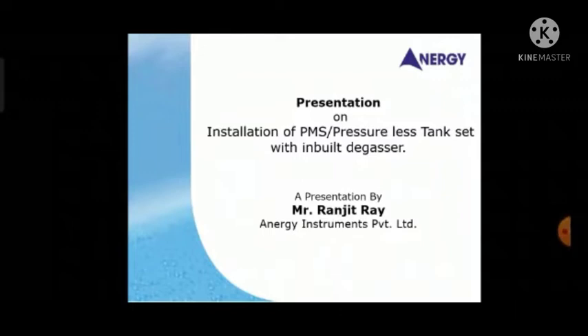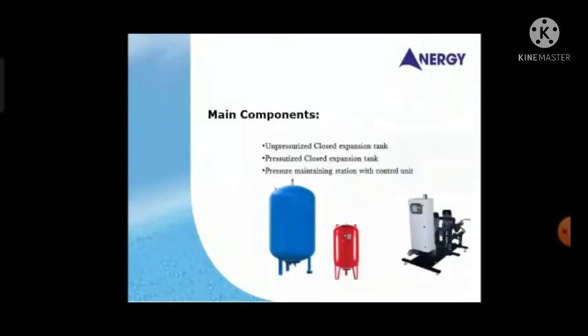This video is for installation guidance for the pressure maintaining station, which is also known as a pressureless tank set with inbuilt degasser, and it is also known by some other name in the market. There are three main components of this system. There is one unpressurized tank, larger in size. Then we have the pressurized tank, smaller than the unpressurized one, and then we have the pumping set, which has two pumps, one working and one standby.